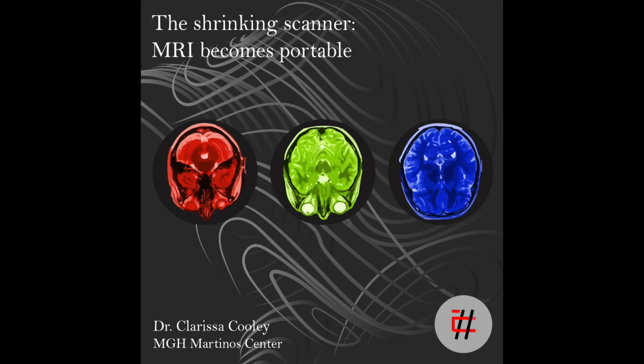Sure. So most conventional scanners use a large superconducting magnet to create the main static field called the B0 field. And the strength is usually 1.5 or 3 Tesla, and it's a very uniform field. And the strong uniform field basically aligns the magnetization of the protons in the water molecules in our body. And then when we excite the protons with an alternating magnetic field, the protons precess at a characteristic frequency that's proportional to the static field strength.